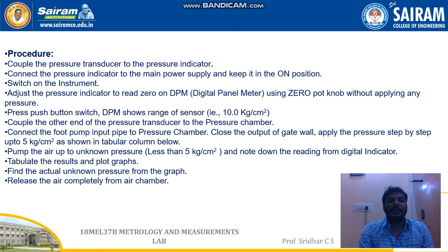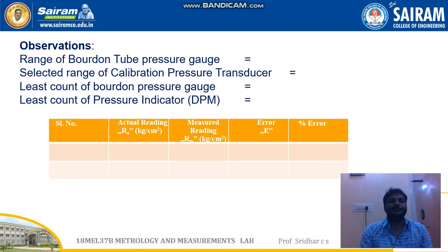Finally, we need to tabulate the results, plot the graph and find the actual unknown pressure from the graph, and we need to release the air completely from the air chamber. Now we can see the observations. The observations required are the range of the Bourdon pressure gauge, the selected range of the calibration pressure transducer, the least count of the Bourdon pressure gauge, and the least count of the pressure indicator.